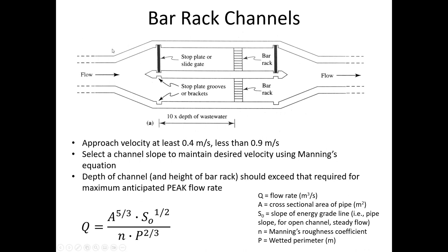Because remember, in the channel before you get to the bar rack, we've got tons of debris. Maybe not tons, but there's debris there, and the whole point of the bar rack is to get it out. But if the water's moving too slowly, it'll just settle to the bottom of the channel, and then someone has to climb in there and rake it towards the bar rack.